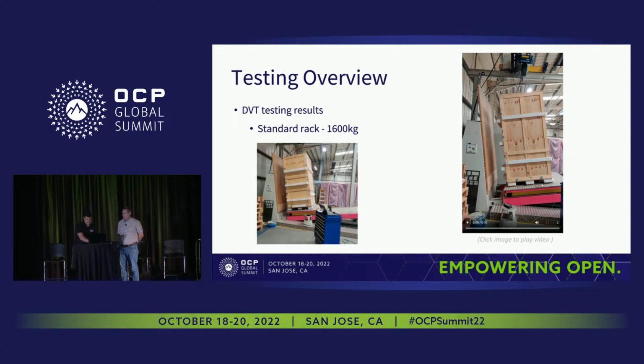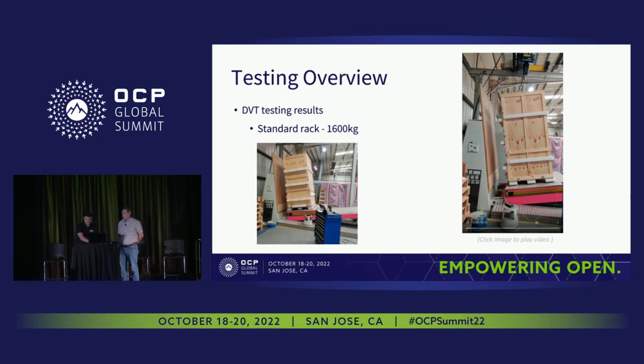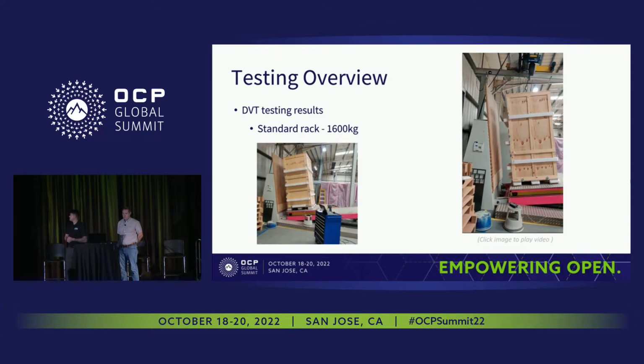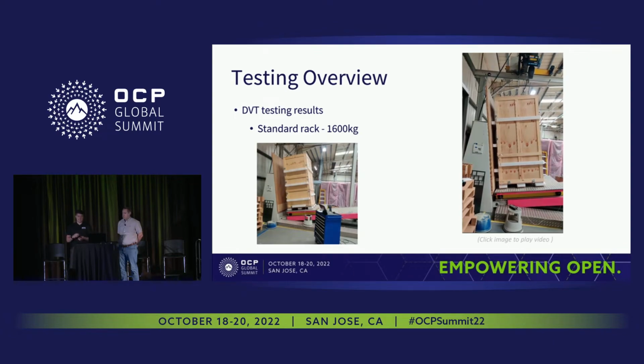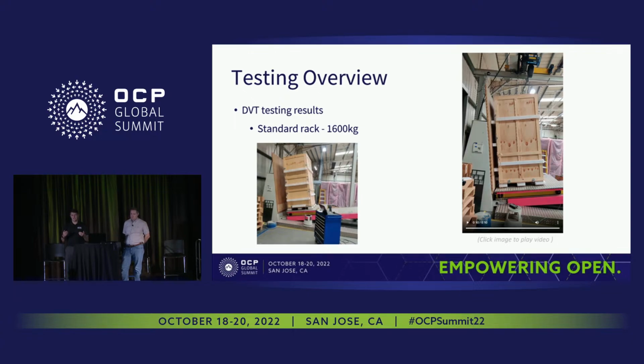So here, I'm just going to see if this video works. It's a video of the front impact of the rack. That is one of the more difficult tests that we had to pass with the ORV3 rack. Because of the toolless design of the shelves that the equipment goes into, there's the risk of delatching, which is a big concern during transport. So this was one of the most challenging tests that we had to pass. This configuration is the 1,600 kilo payload, and this was the middle beam position. And we passed that, which was great.